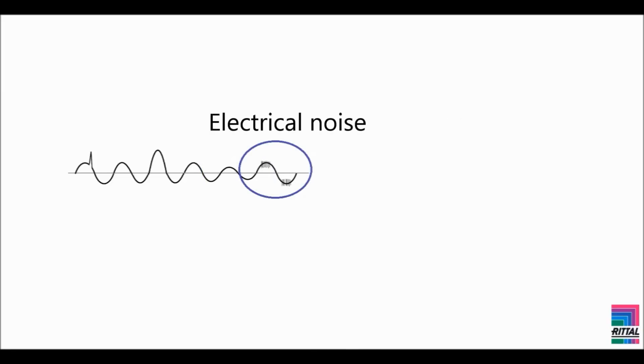Electrical noise: Very high-frequency oscillations superimposed on the supply sine wave. This can be caused by lightning strikes, load switching, cable faults, or nearby radio frequency equipment. Electrical noise can cause data corruption and hanging computers.